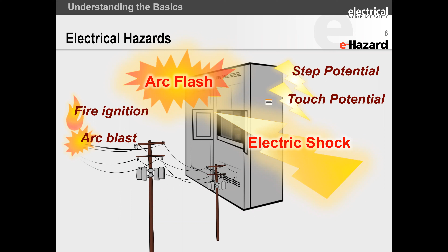So voltage levels, what is high voltage, what is low voltage? Low voltage generally is considered voltages below 1,000 volts. Now OSHA decided to take a bit of a different angle, using a simple value of 600 volts. OSHA doesn't directly state that high voltage is this and low voltage is this, but what they state is: below 600 volts is considered low voltage, above 600 volts it has high voltage rules.